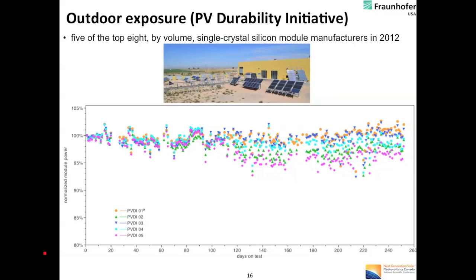So it's conceivable that what's happening here is that as we've headed into spring in Albuquerque, the aerosols in the air have changed. We have a bluer spectrum, for example. And so some modules with a different encapsulant may be letting less blue light through, and so their performance starts to drop. So you've got essentially at least two things going on. Perhaps you don't really understand their performance enough yet based on their nameplate rating. And again, yeah, they very definitely could be degrading. I hope it's the first, but we're about to find out.